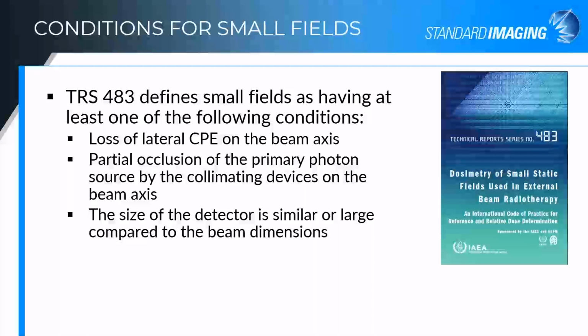TRS 483, small fields have at least one of these three conditions, and may have more than one. Loss of lateral charge particle equilibrium on the beam axis. They can have partial occlusion or blocking of the primary photon source by the collimating devices that are along the beam on the beam axis. Or the size of the detector is similar to or large compared to the beam dimensions.